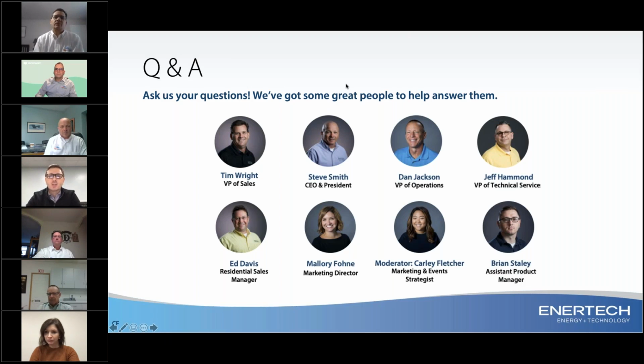Moving on, I got a question here from Jake Marin. He says, do you have design options to run at higher temperatures up to 180 degrees Fahrenheit using a boiler to supplement the heat pump during the peak periods? And he states that most buildings have fin and tube baseboards that's going to require higher than 135 degrees Fahrenheit temps during the colder periods. I think Jeff might be able to tackle that one.